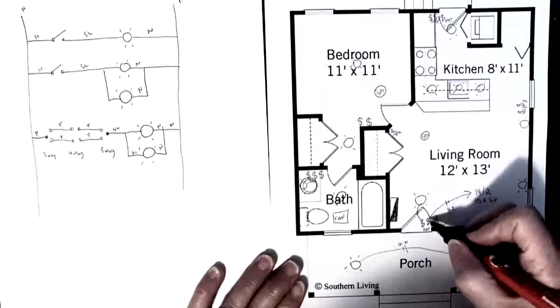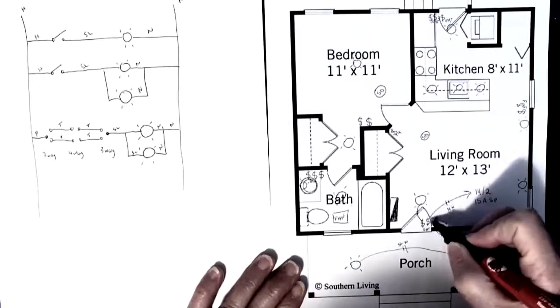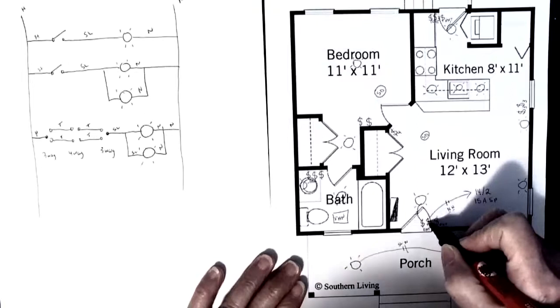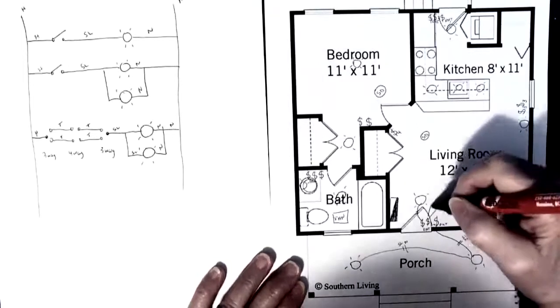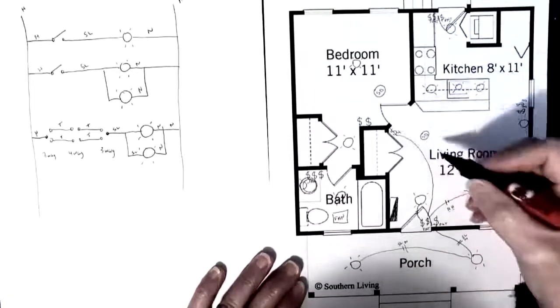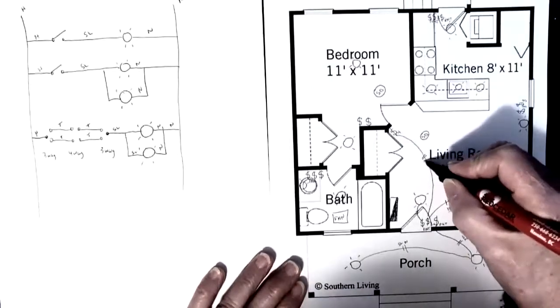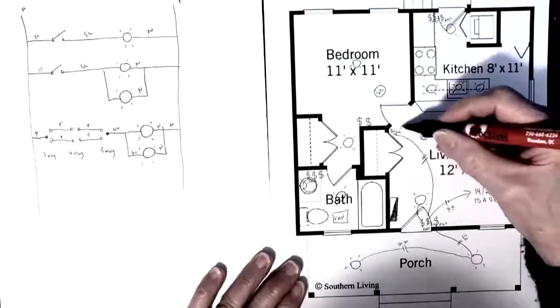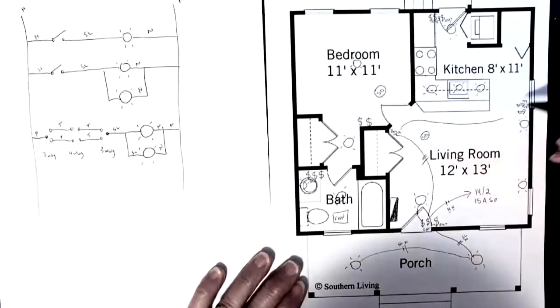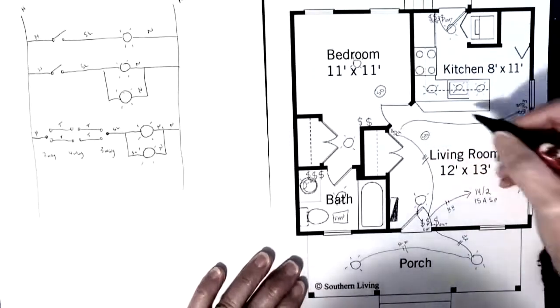So we already have power here, so we have a hot and neutral, so our hot goes into our three-way switch. We have to take a wire over to our four-way switch, and in that wire are going to be two travelers and a neutral, and then another wire over to the last three-way.